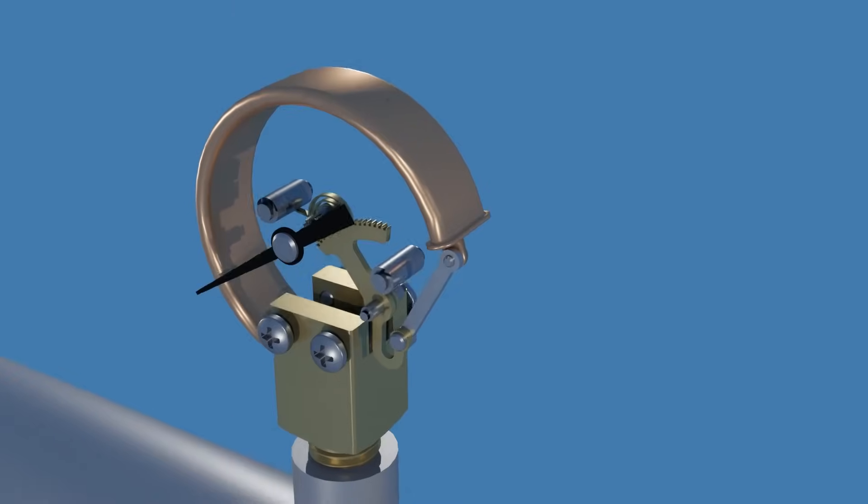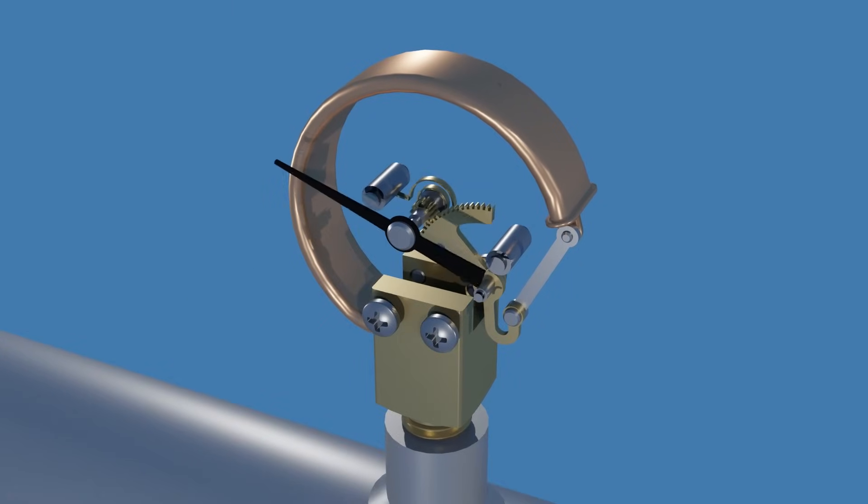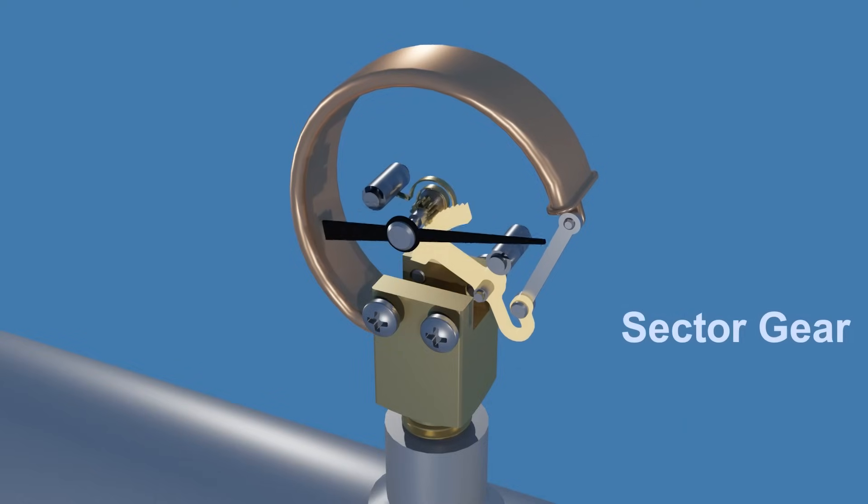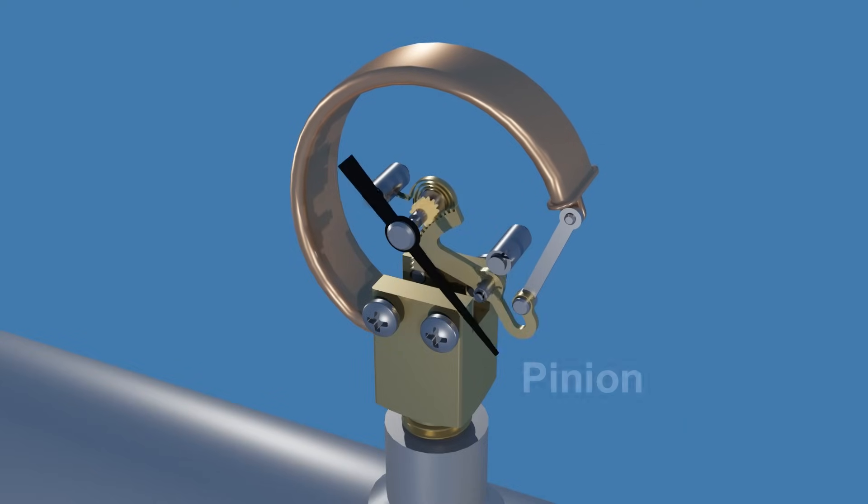As the Bourdon tube straightens, it transmits its linear motion through the connecting link. That drives the sector gear, that meshes with the pinion driving the pointer.